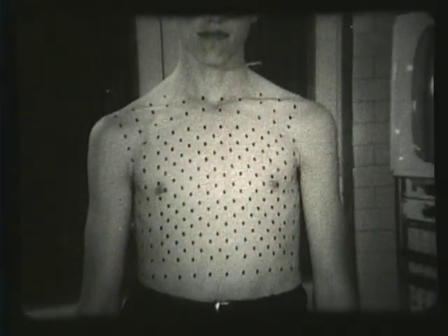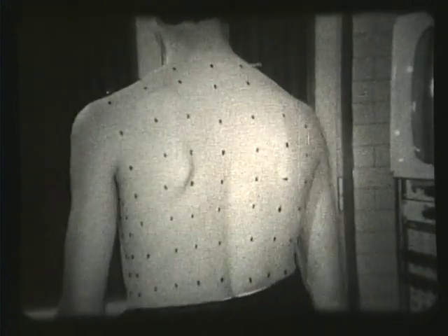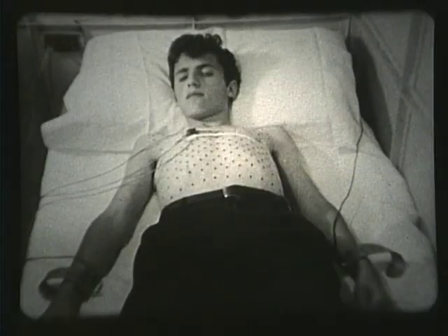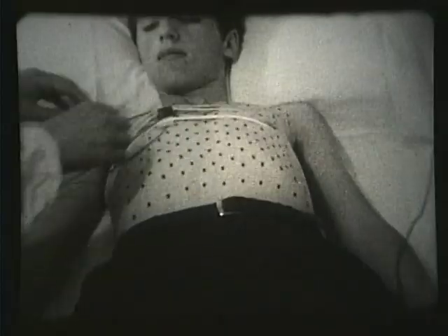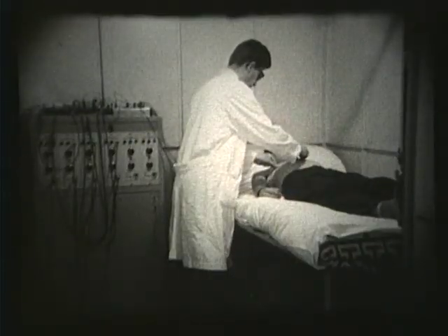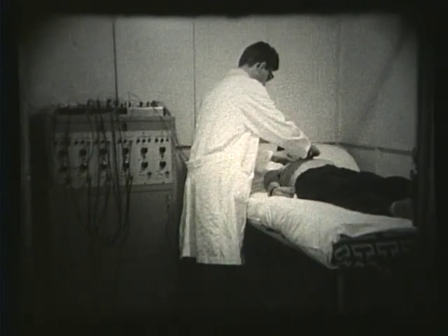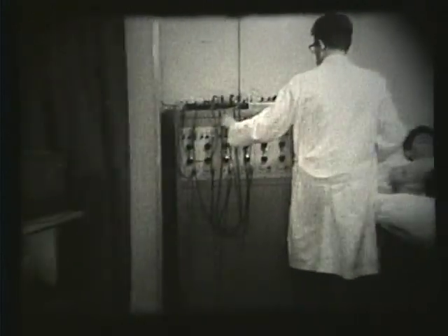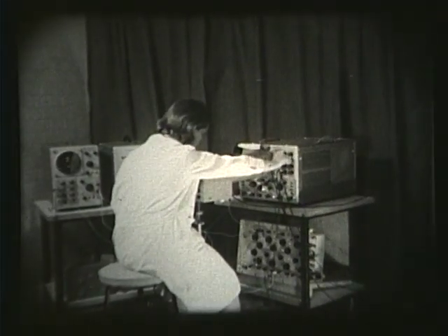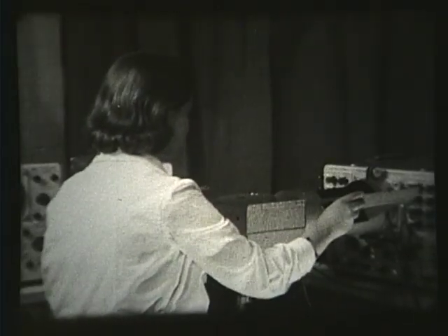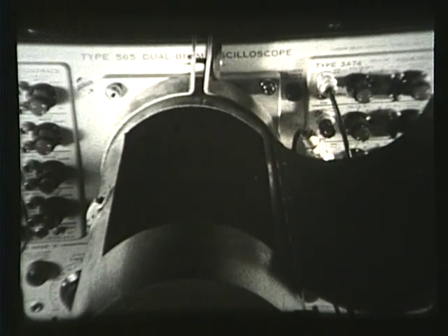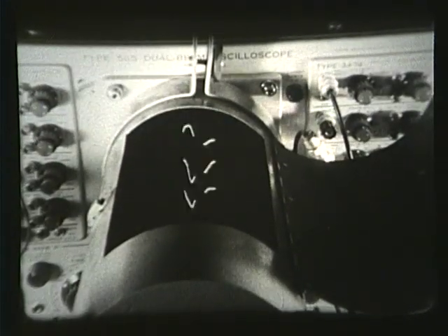First, the patient is photographed, then laid on a couch in a Faraday cage. 250 electrocardiograms are sequentially recorded by leading off from the spots that had been marked on the skin. 3 to 6 simultaneous recordings are taken each time using a multi-beam cathode ray oscilloscope. The tracings are registered on a film and optically enlarged.